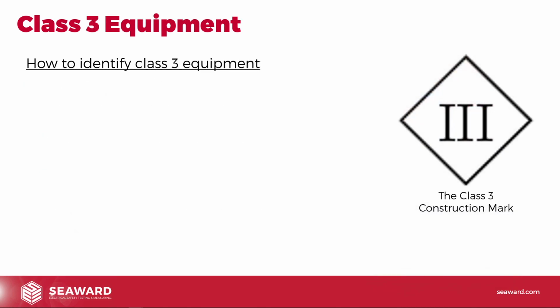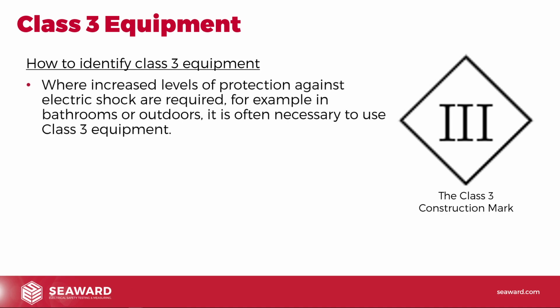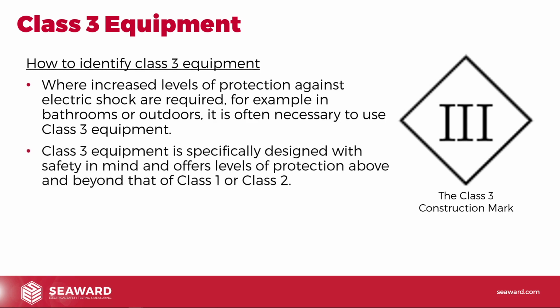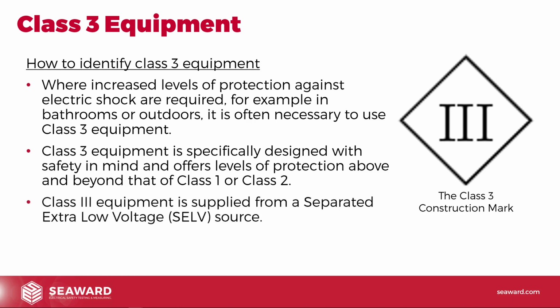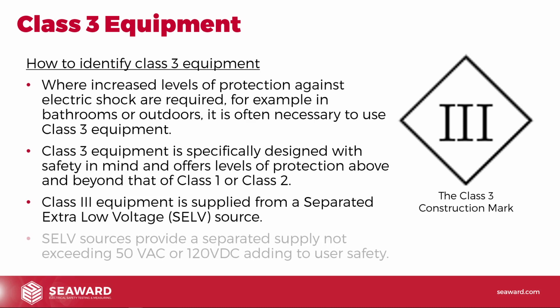So the final one, and again quite rare in this case, is class 3 equipment. So where increased levels of protection against electric shock are required, for example in bathrooms or outdoors, it's often necessary to use class 3 equipment. Class 3 equipment is specifically designed with safety in mind and offers levels of protection above and beyond that of Class 1 or Class 2. Class 3 equipment is supplied from a separated extra low voltage source. So generally these will be powered from a separate transformer, which will be a source of separated extra low voltage.